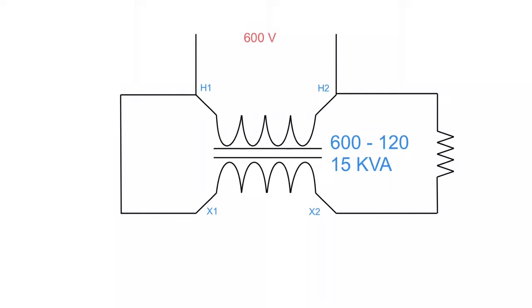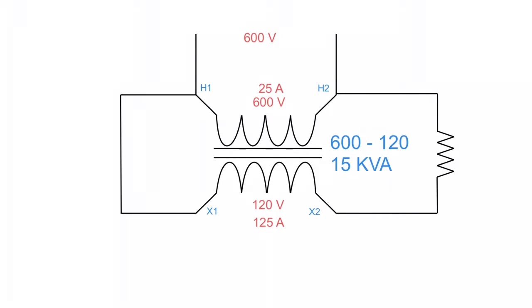As with any transformer, the first step is to determine the rating of your windings. This is a 600 to 120 volt, 15 kVA transformer, meaning the high side is rated at 600 volts and the low side at 120 volts. We use the 15 kVA to determine current through each winding: 15,000 divided by 600 gives 25 amps rated on the high side, and 15,000 divided by 120 volts gives 125 amps rated on the low side.